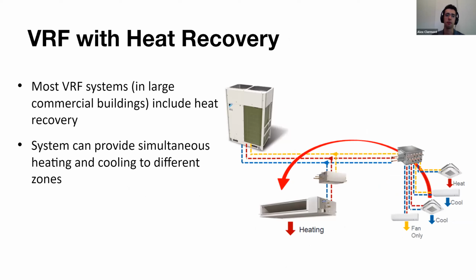This is VRF with heat recovery. It's only available if there's three-phase power available for the outdoor unit. But with heat recovery, you can actually have different indoor units be in different modes. One indoor unit can be in heating while another is in cooling. There's actually an extra component here, if you notice, that makes this happen, and it is those branch boxes.